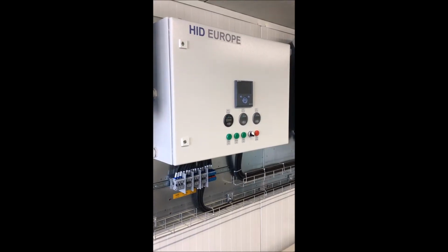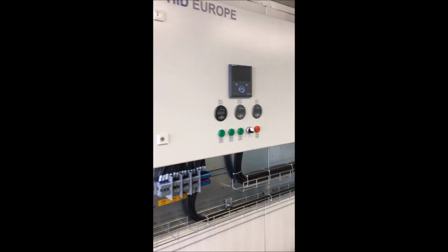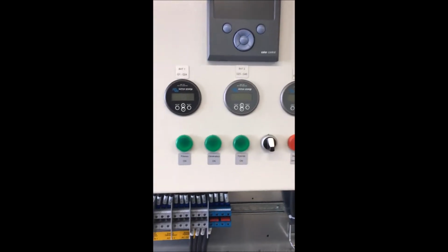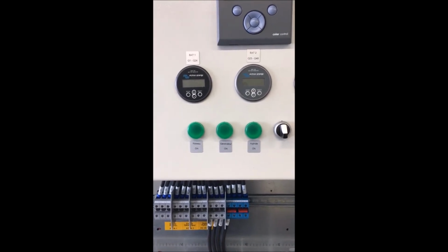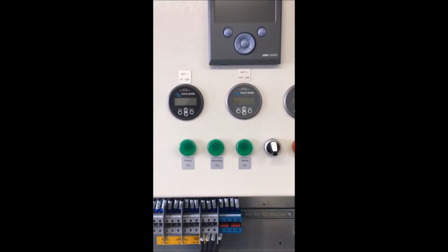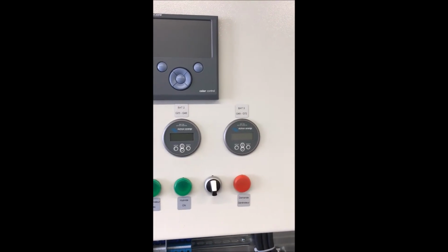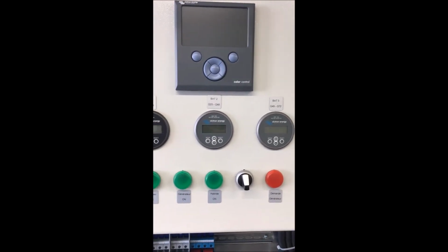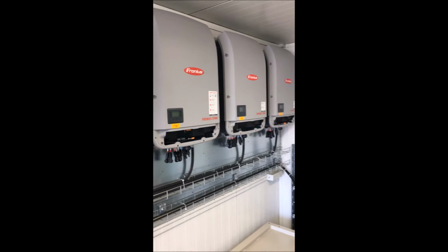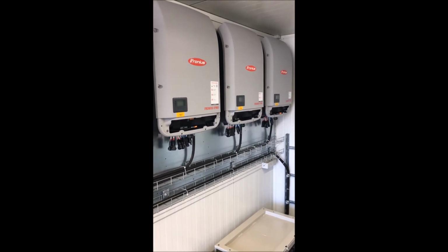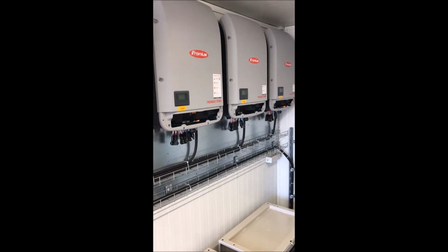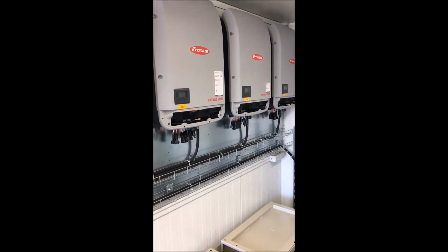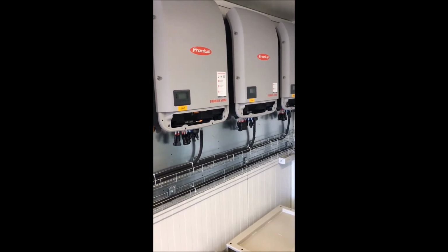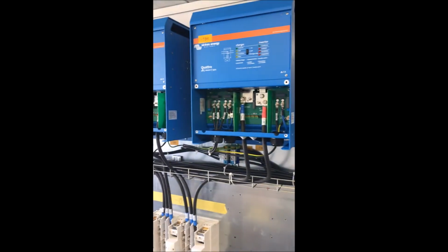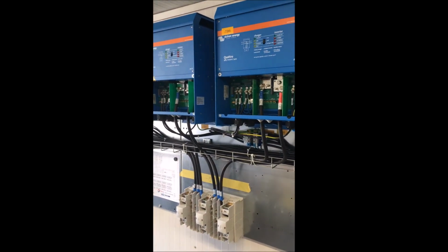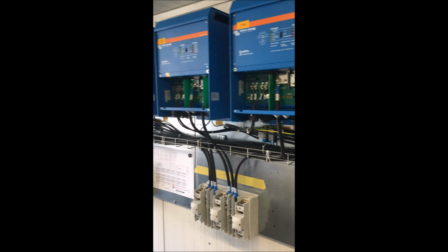Here you can see our generation management system, and also we have signal lights indicating whether the grid, the generator or the system is functioning. Plus there are battery monitors showing the status of each battery string. At the end of the container we have our PV inverters, which take the solar energy and convert it from DC to AC, so it can be sent to the Victron battery inverters to then be converted back to DC and stored in the batteries.